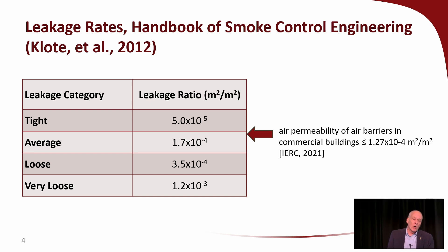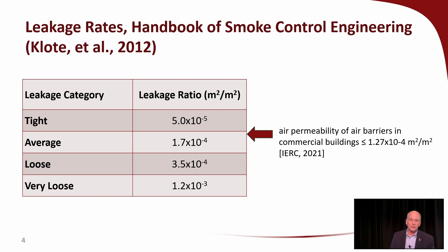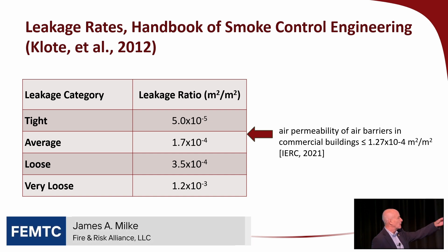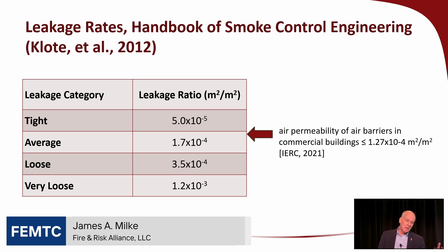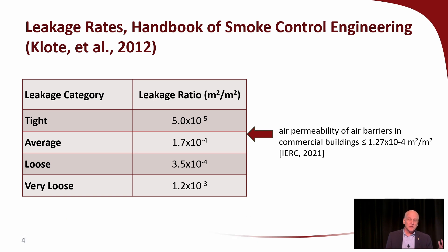For exterior walls, there are leakage categories in the table: tight, average, loose, and very loose. But what do you think — is that wall loose? Is it very loose? There's no description of what constitutes a loose wall. And this data in the handbook is from information from buildings in North America, largely from the 1970s.